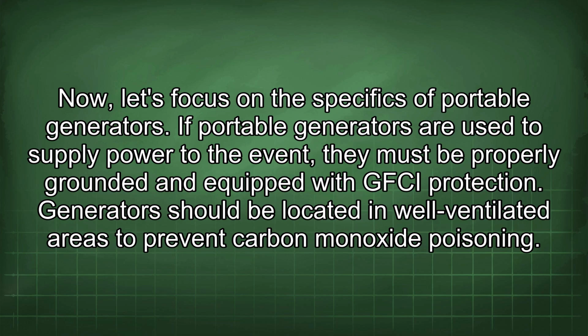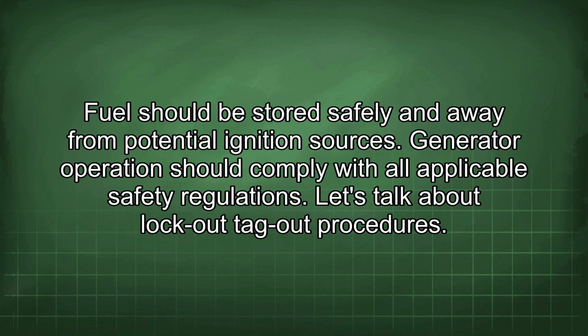If portable generators are used to supply power to the event, they must be properly grounded and equipped with GFCI protection. Generators should be located in well-ventilated areas to prevent carbon monoxide poisoning. Fuel should be stored safely and away from potential ignition sources. Generator operation should comply with all applicable safety regulations.